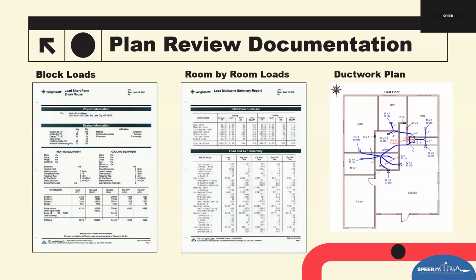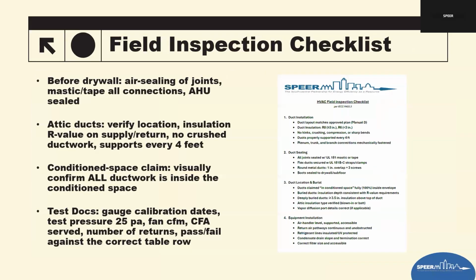When it's not, you have friction loss, you have turbulence, you have buildup of static pressure inside the ductwork. As Robert just said, if we test the CFM, where did the air go? The ducts pass the duct test because there's not a lot of leakage, but why am I not getting the CFM that I need? A lot of times it's trapped in the duct system, and that comes down to proper duct installation. We'll see pictures of those in just a second.